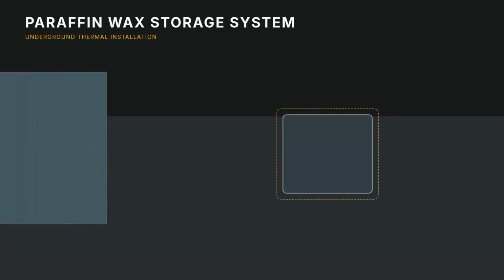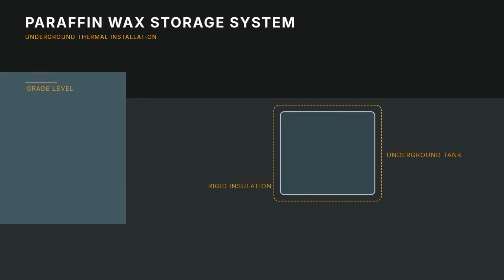Second, your available underground installation space. The tank must sit at a minimum of 4 feet below grade to access stable ground temperature. This requires either an accessible crawl space, a basement with drainage capability, or an exterior below-grade installation adjacent to the building foundation. Measure your available excavation footprint before specifying tank dimensions.